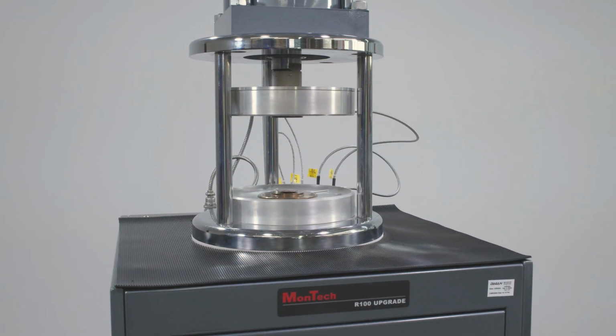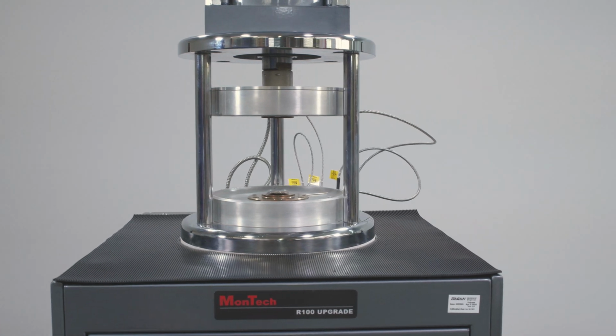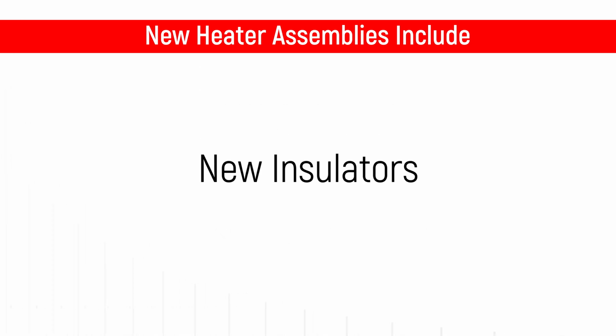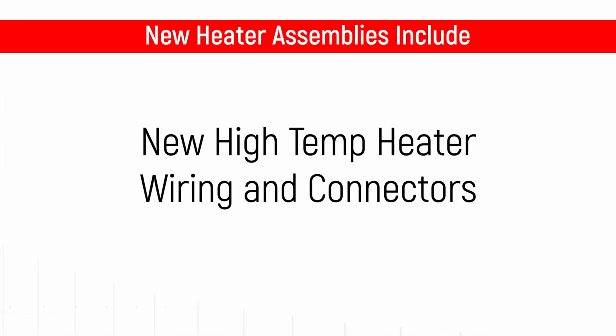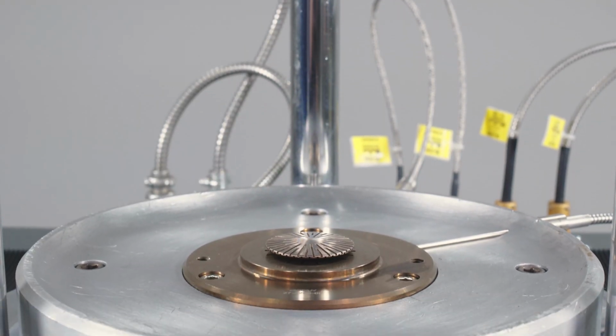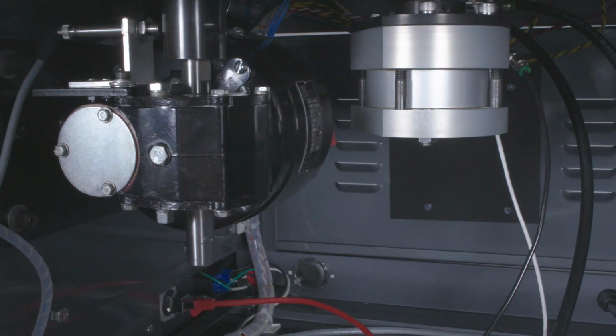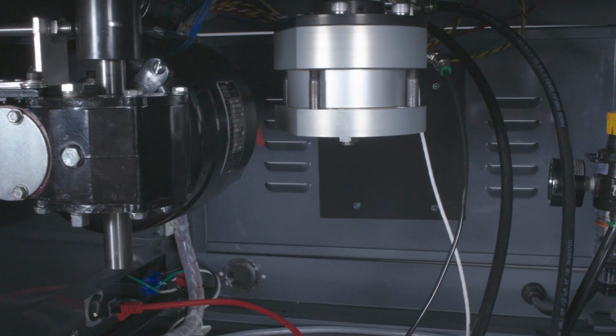Next, we install new heater assemblies in both the upper and lower platens. This includes new temperature sensors, heaters, thermal switches, insulators, high temperature heater wiring and connectors. New upper and lower dies and a new rotor are also included. The central shaft assembly is replaced and new bearings are installed.